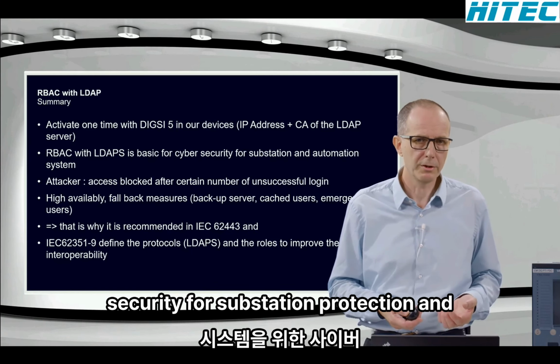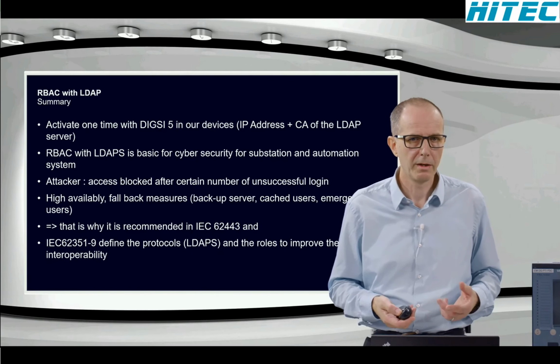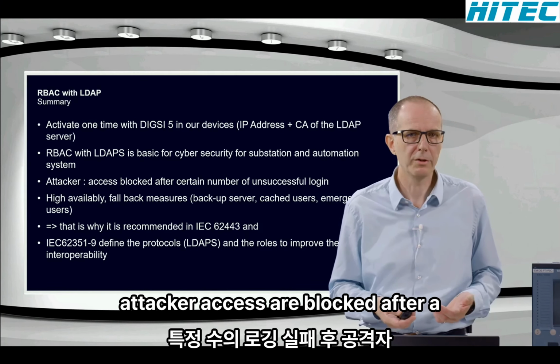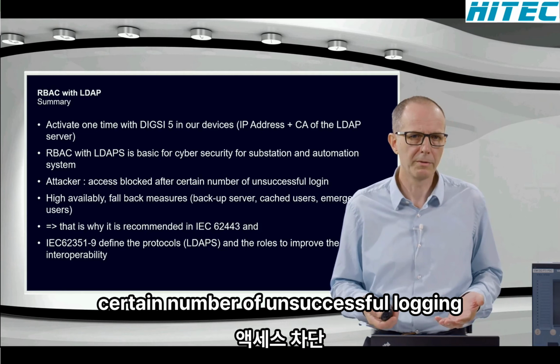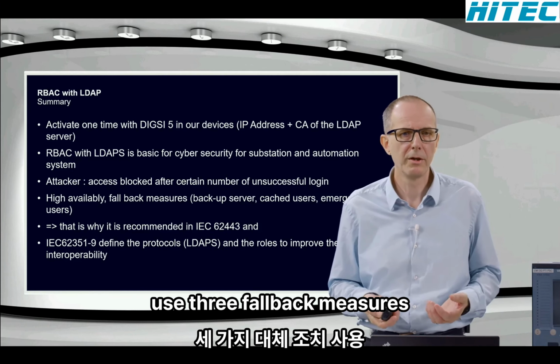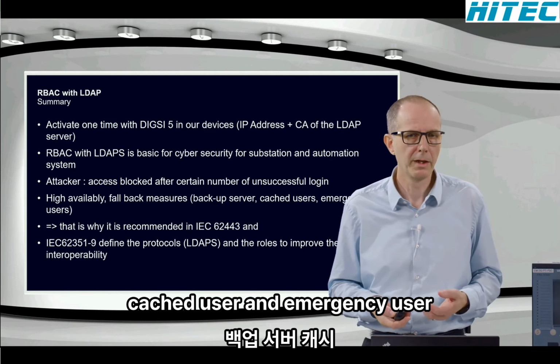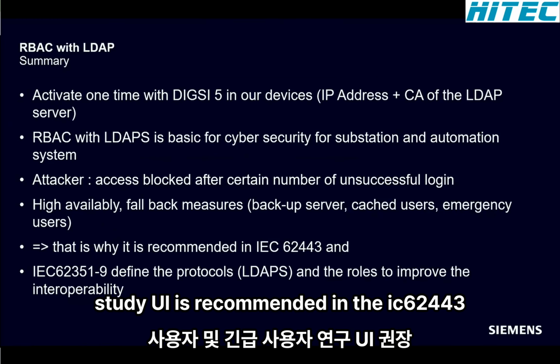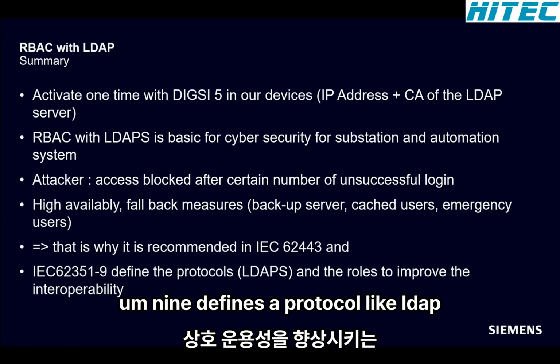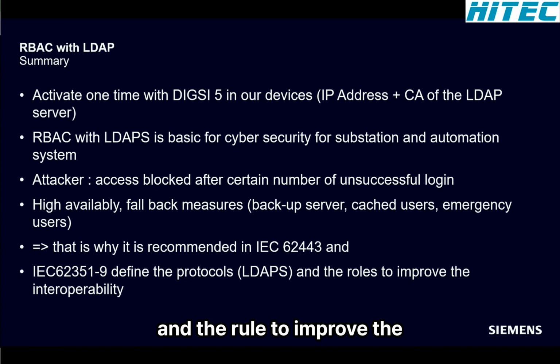RBAC with LDAP is basic for cybersecurity, for substation protection and automation systems. Attacker access is blocked after a certain number of unsuccessful logins. It is possible to have high availability due to 3 fallback measures: the backup server, cached user, and emergency user. This is recommended in IEC 62443, and IEC 62351-9 defines protocols like LDAP secured by TLS and the role to improve interoperability.